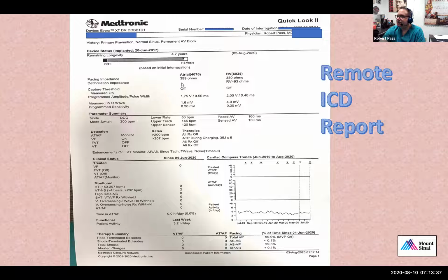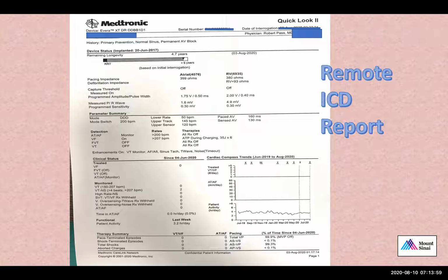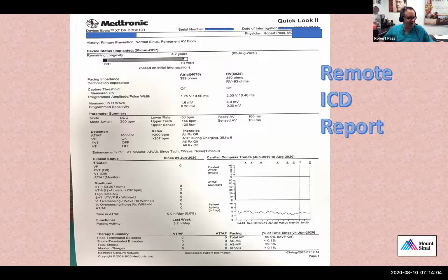So we can see here the impedance to pacing in both the atrial and the ventricular leads. And this can be compared from download to download in order to confirm that. And what does the pace impedance tell us? Sergey, do you have any idea what the pacing impedance is giving us an idea about in regards to pacing leads? No idea. Okay, I like that, a man who tells the truth.